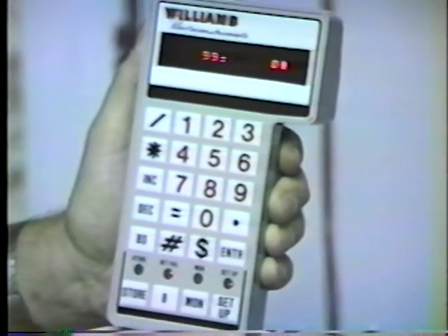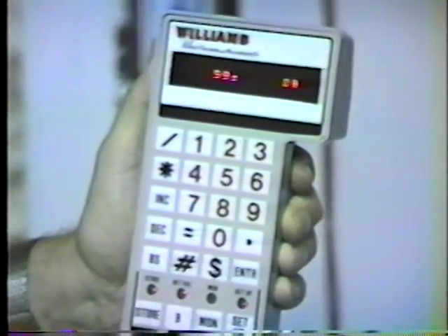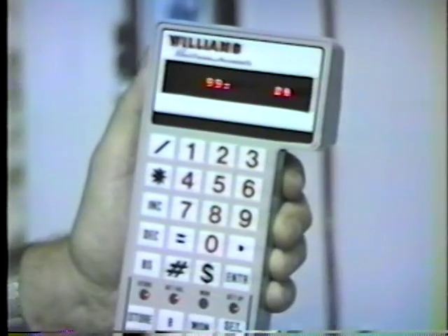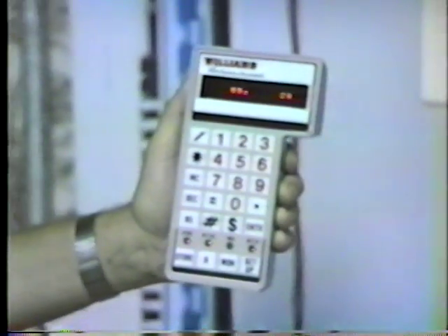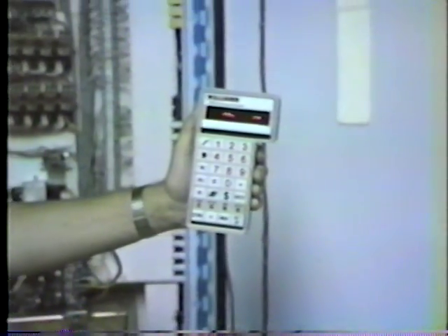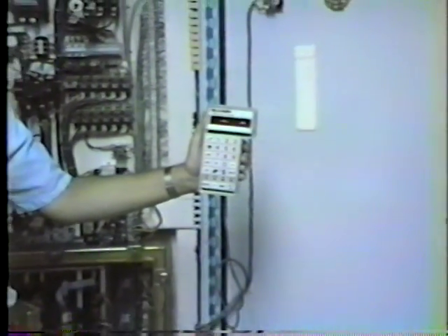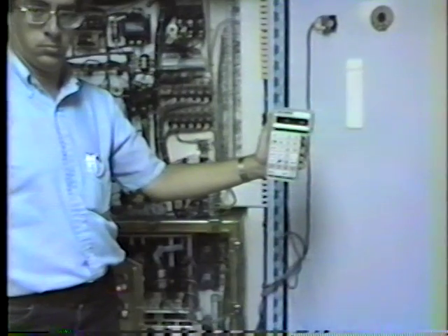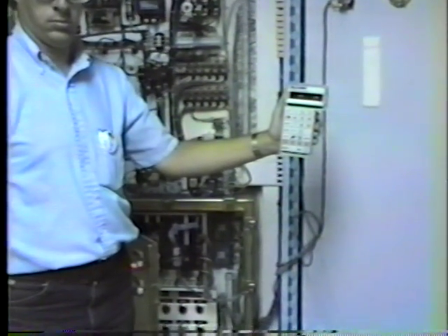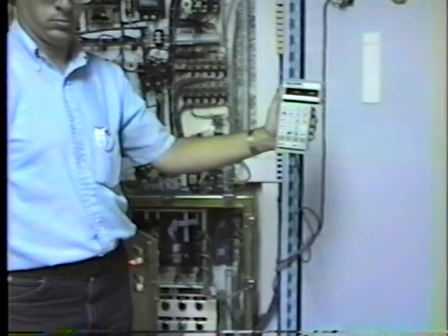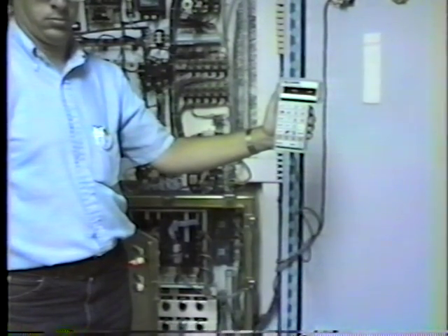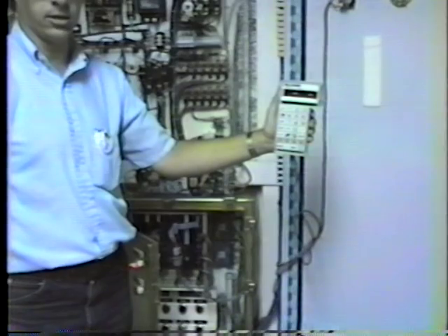Now you have to store it. All right. And sure enough, now the system will start back up, and we are now indicating pulverizer ready to start. Okay. Now that's the only way that you can get the pulverizer to start again. You must acknowledge the fact that you had a bit failure in the computer, reset it to 0, and store that value. That is correct.